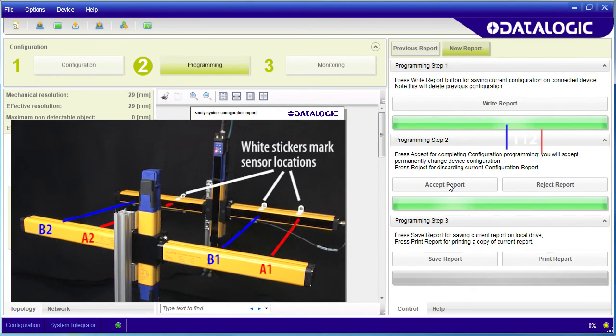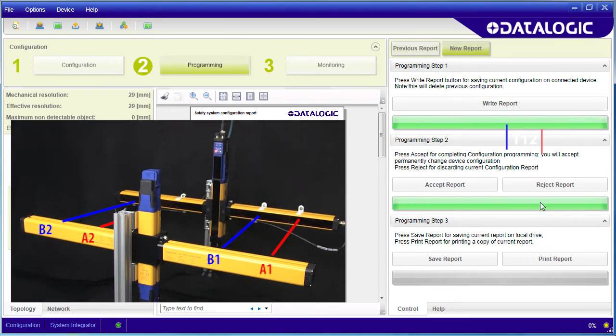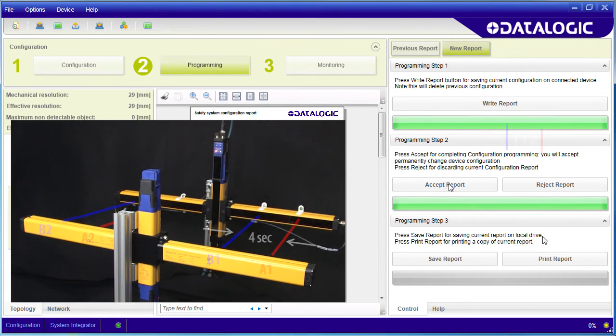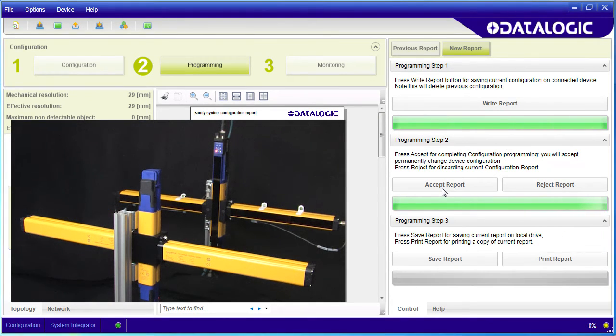Let's try it. Remember, we set this up with the max time between here and here is 4 seconds. So we have to move faster than that to initiate muting. Also, the sensor spacing is critical.